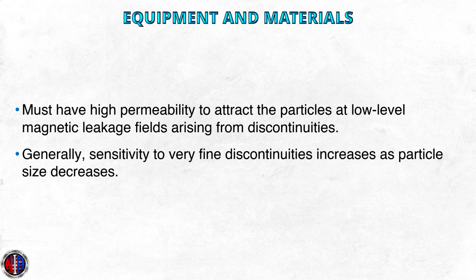The size and shape of magnetic particles play an important role in how they behave. Generally, sensitivity to very fine discontinuities increases as particle size decreases. However, very small particles may adhere to the surface where there is no leakage field and thus form an objectionable background. Conversely, large, heavy particles are not likely to be attracted and held by a weak leakage field as they move over the object surface.